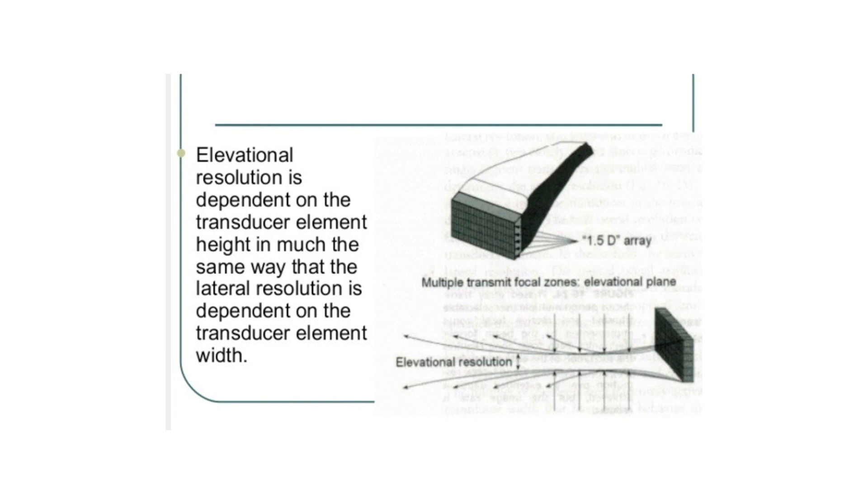So as you can see in this one, elevation resolution is dependent on the transducer element height. So instead of having one tall crystal that comprises the whole face of the transducer, we break it up into smaller crystals that we can focus at a specific point, which will give us that very narrow beam thickness even though we have the five different crystals.